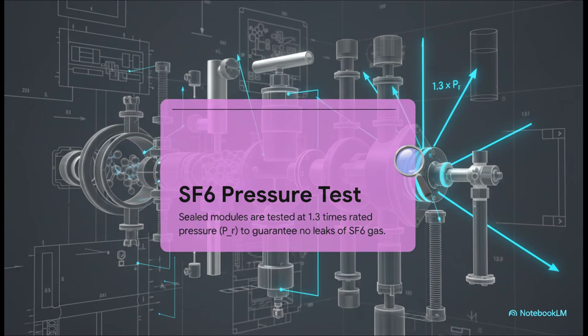Now, this is absolutely crucial. That SF6 gas is the only thing keeping all that voltage contained, so you have to be 100% sure it never leaks. To do that, every single sealed compartment is put through a stress test. They pressurize it to 1.3 times what it'll ever experience in real life just to prove it's perfectly sealed. It's a simple formula, but it's a make-or-break quality check.